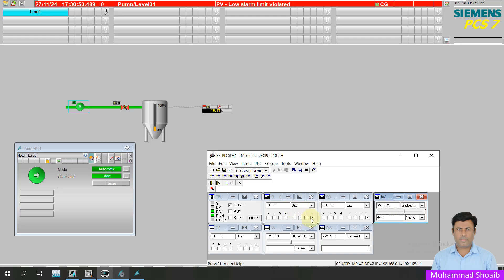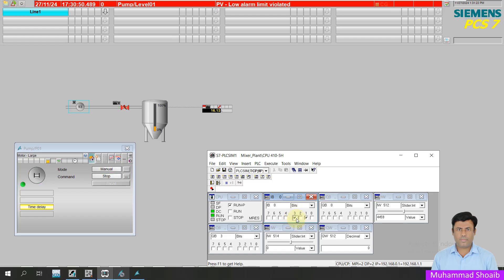Now I will remove the auto mode. As you can see, my operation is bumpless — it did not go into stop mode. Now I will turn on the manual mode. When I click here, you can see the mode has changed to manual mode. If I want to stop the pump, I0.3 is my stop bit. It will receive the stop command, and now through the field push button I can start and stop the pump.